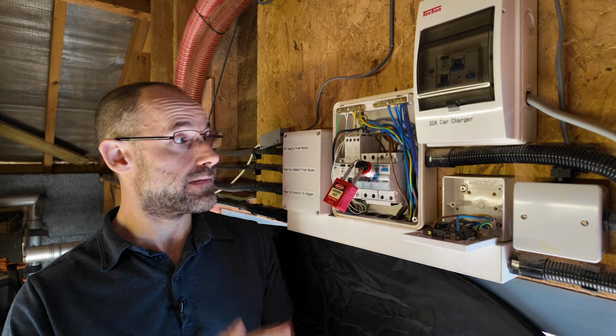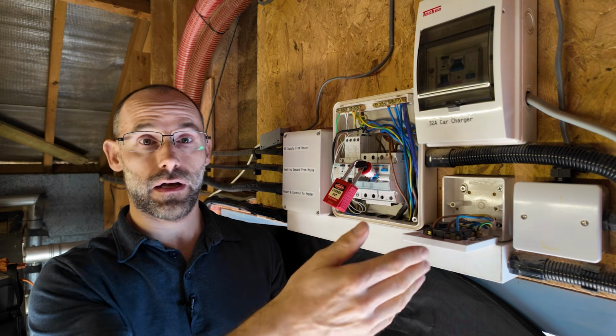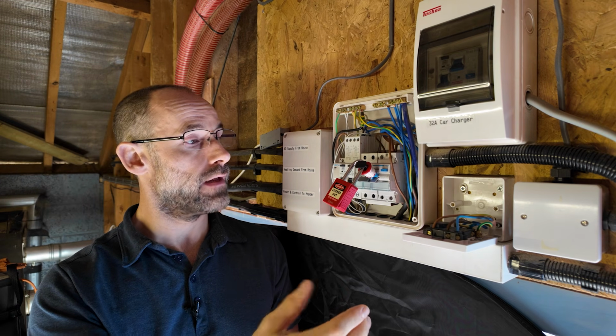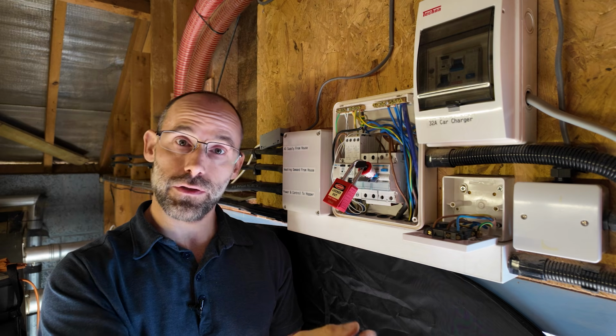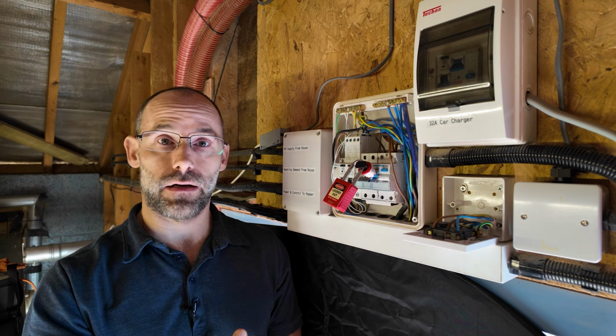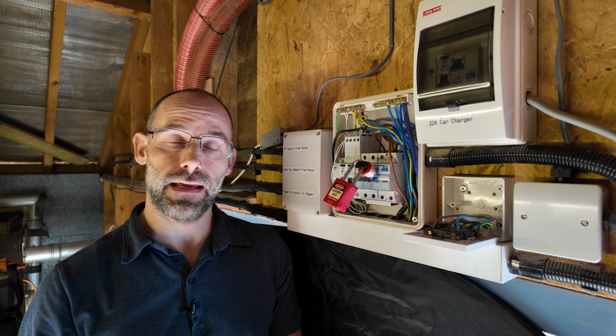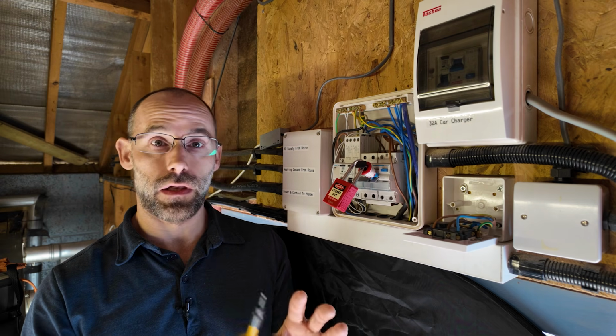All right, so we've completed the dead test. We've checked the continuity of the conductors, we've checked their insulation resistance, and we've checked that when we switch the switch, we are breaking the line conductor. That's that type of polarity. Now here's another type of polarity. This is called the live polarity.